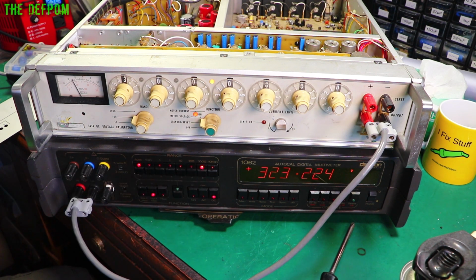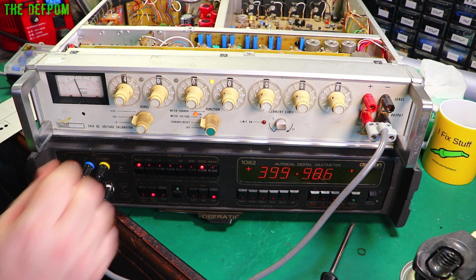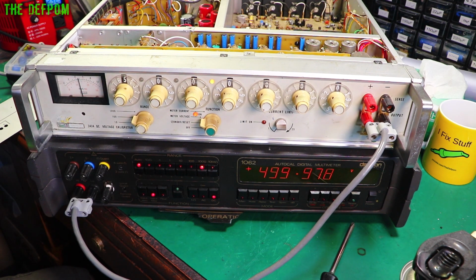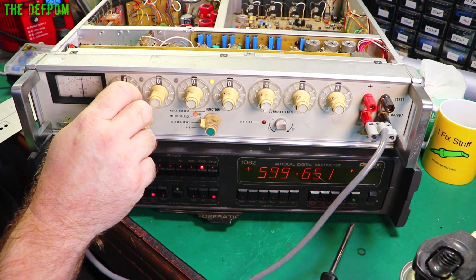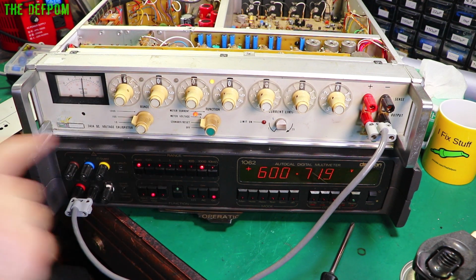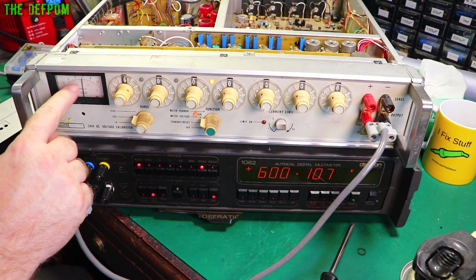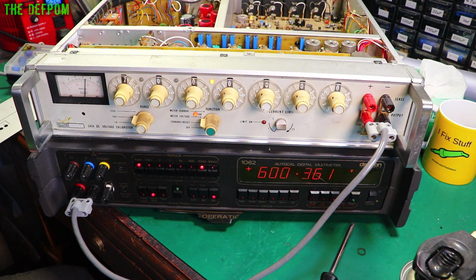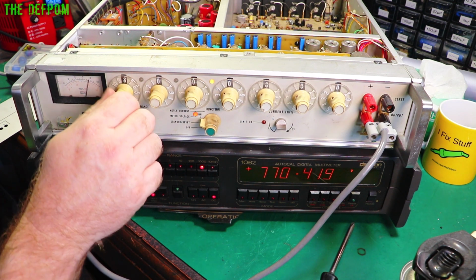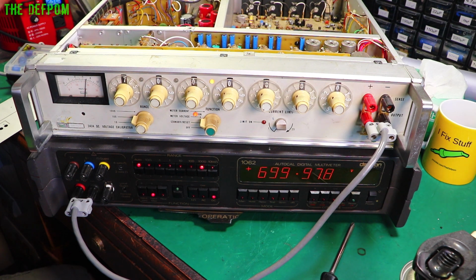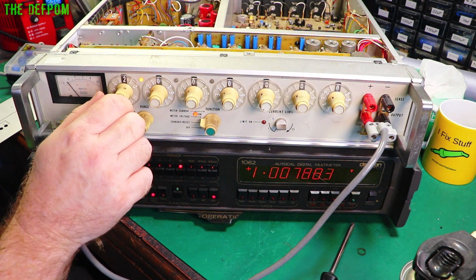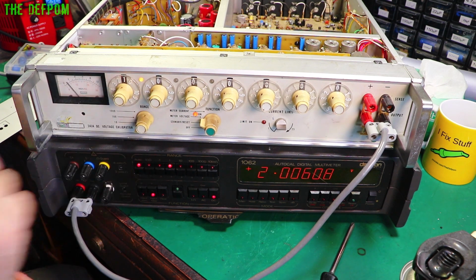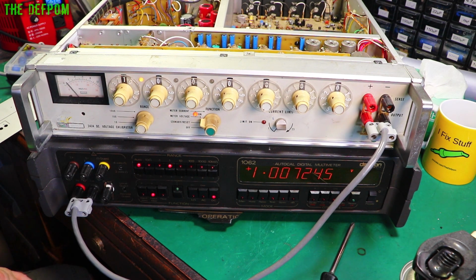So the 300 volt range is still playing up. 400, sitting low. 500, sitting low. Just want to see if any of these start jumping around. 600 still jumping around. Look at that. I can even see the needle bouncing slightly just over here. So that hasn't fixed it by the looks of it. So I don't completely trust this whole switch assembly here. I'm just not confident that's okay, because that's the only thing that's different. This is basically this switch assembly and the dividing networks. So now I've got this error on 1 volt. It's actually got worse. Imagine that.